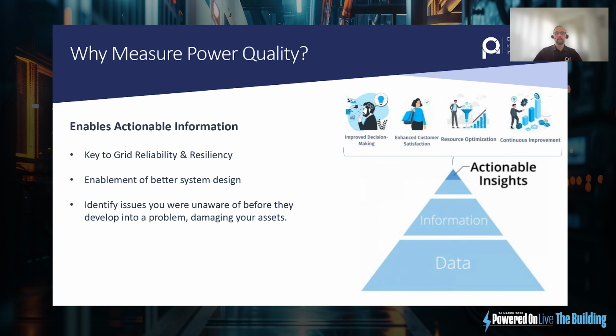So why should we monitor the power quality? If you monitor the power quality, you know how the system situation is. You know what you're getting into before connecting your own equipment in. So if you're upgrading or putting new EV chargers in, you've got a baseline to understand how healthy the system is that I'm plugging this new equipment into. That's the most important thing, I think, that's critical. So having a pre-survey done or putting in some online monitoring that's fixed, so that you've got a continual recording over time that you can go back and look at as you've upgraded. Has it affected anything, or is anything affecting you? That's ultimately the key thing really, is knowing that your equipment's going to be healthy, that you're investing in.